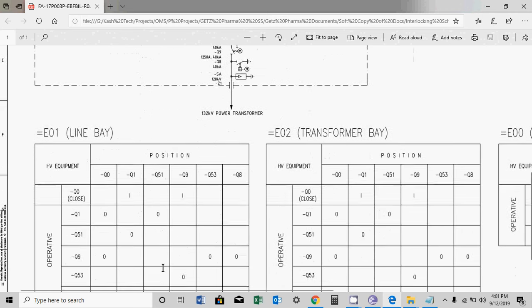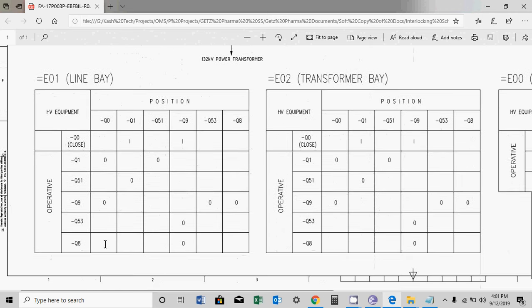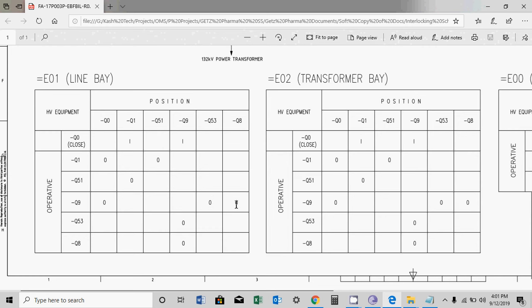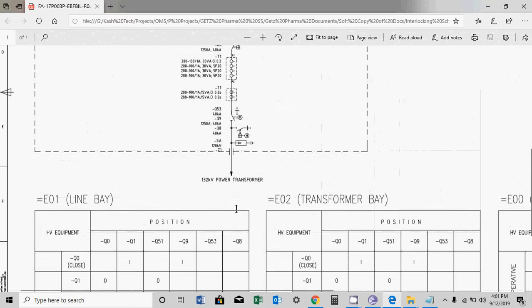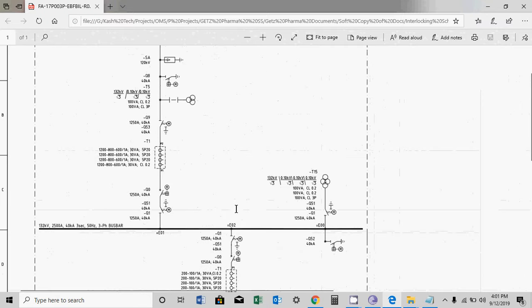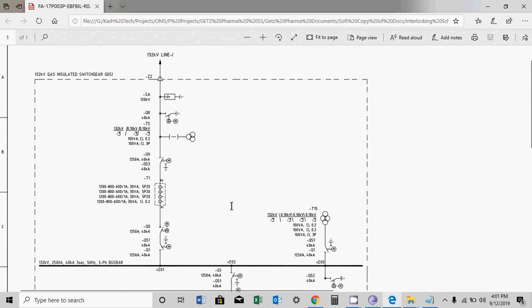Then you can see Q9, this is the line isolator. If you want to close it, you have to first make sure the breaker Q0 should be open, the earth switch Q53 should be open, and Q8 should be open. We will see what is Q53 and Q8. Q8 is a line earth switch, so it should be open. And Q53 is the earth switch of the line isolator itself. So this earth switch should be open, Q8 should be open, and the breaker should be open. Then you can close this isolator.